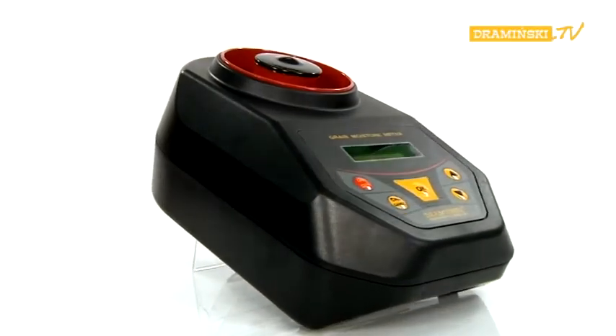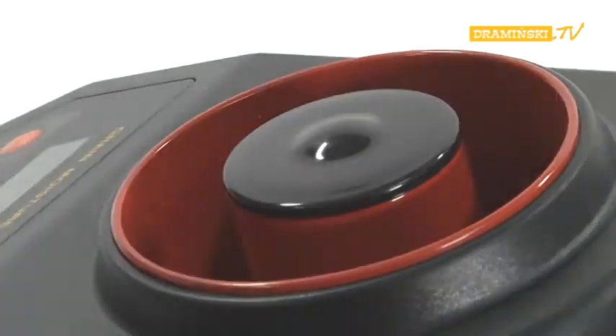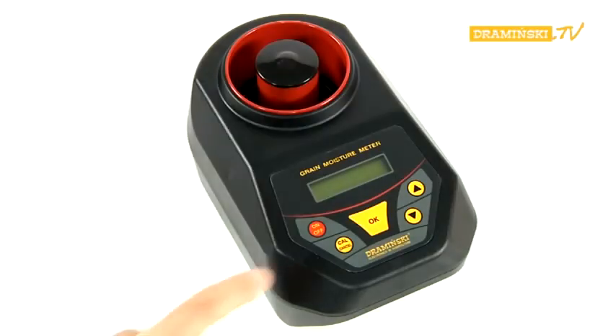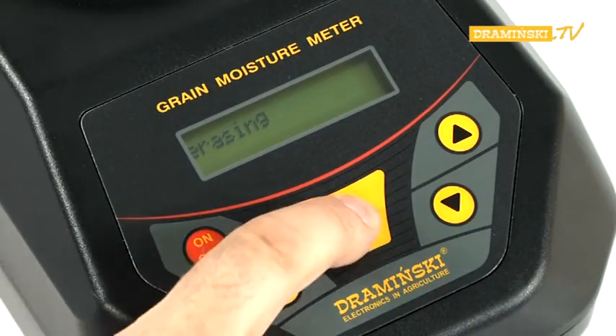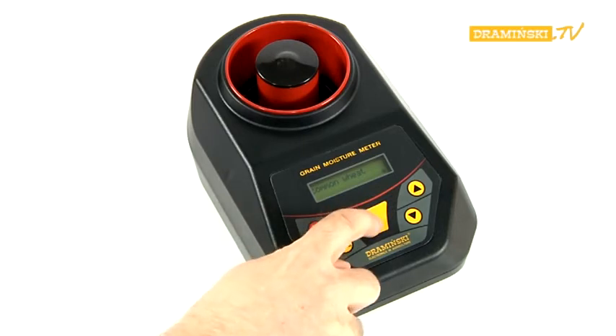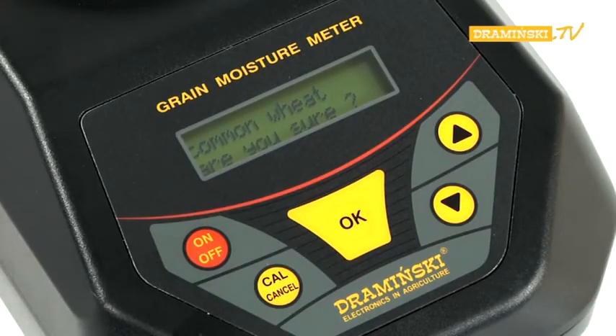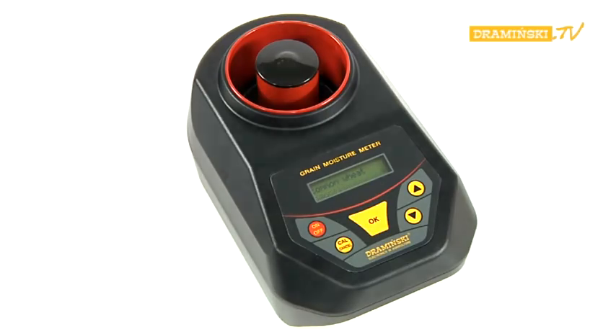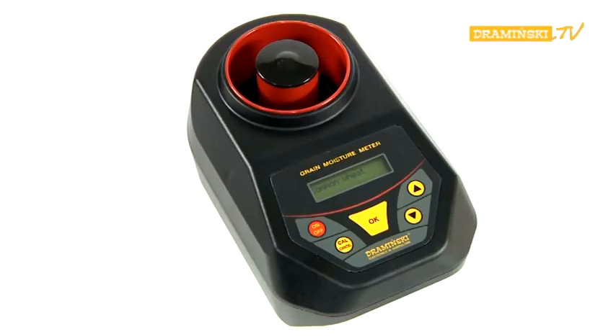In addition to the modifying function, the GMM also has an erasing mode, which restores the factory settings for the chosen sample name. To use this mode, turn on the power supply with the on-off button while the cal button is pressed. Use the arrow button to choose the erasing function and confirm it by pressing OK. Choose the desired sample name with the arrow buttons and confirm with OK. A question asking whether you are confident of your choice will appear. To confirm the erasing process, press OK, or press cal to interrupt. After a successful erasing process, 'OK' will appear on the display and the star symbol will disappear. To leave the erase mode, switch off the power supply.